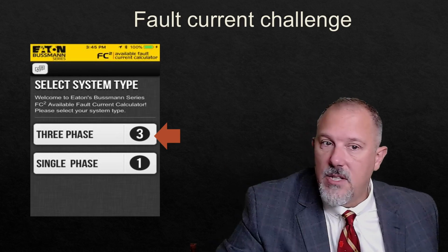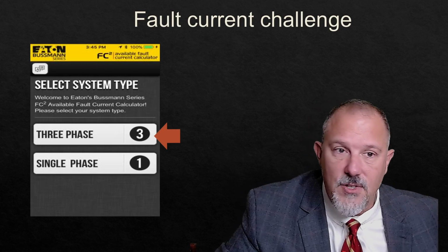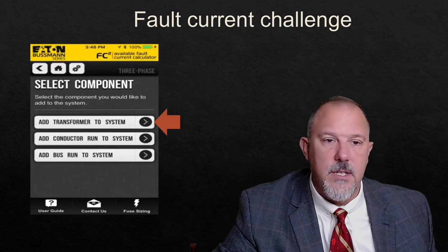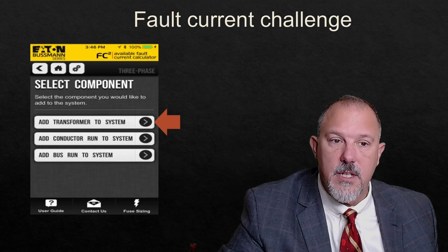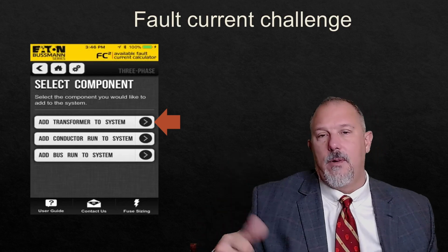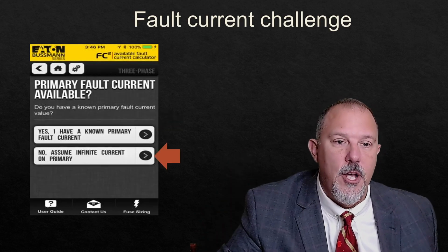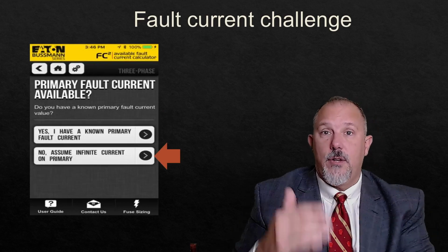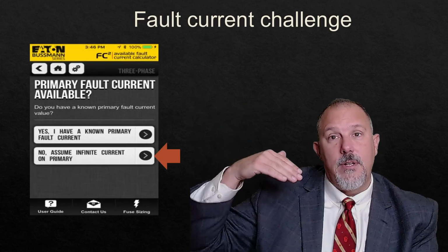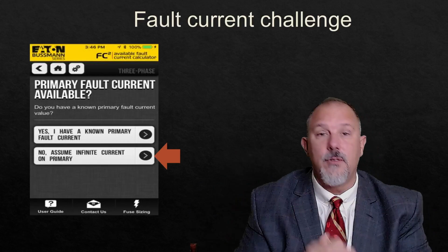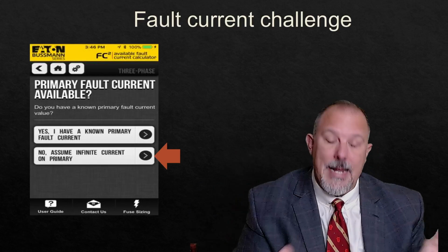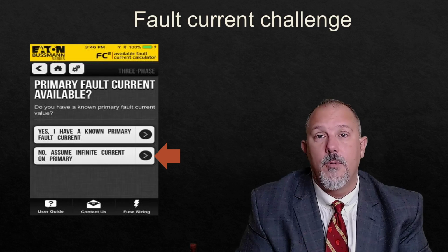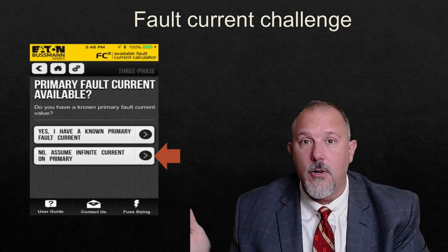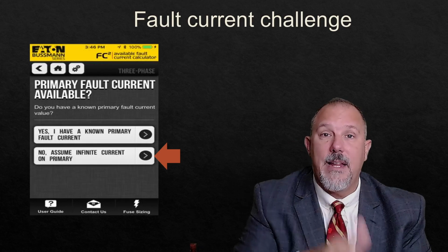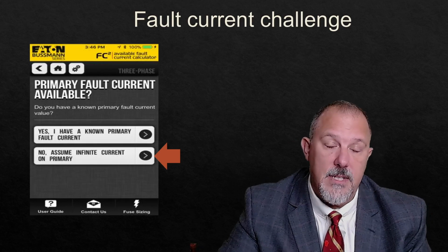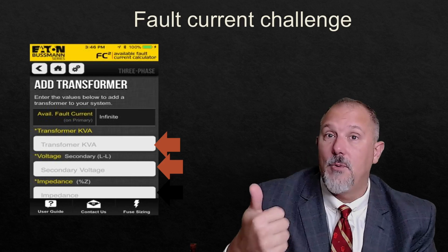So to model this system, we're going to enter three phase. We're going to say add to the system. We can add a transformer, a conductor run, or a bus run. We're going to add a transformer. If you have a transformer and you know what the utility's fault current is on the line side of that transformer, you could enter it. If you did a calculation down to the primary of a transformer, you know what that number is. You can take that number and take it on down. I'm going to assume an infinite bus in this application. That's how I did my manual calculation.